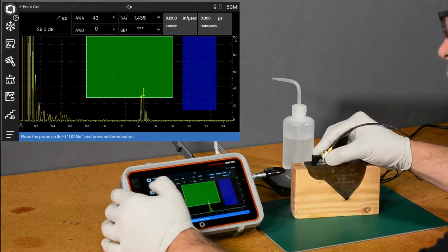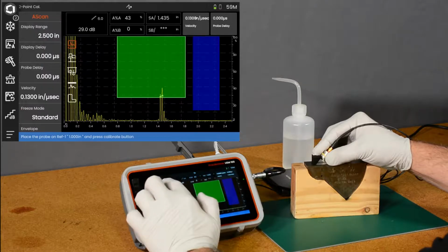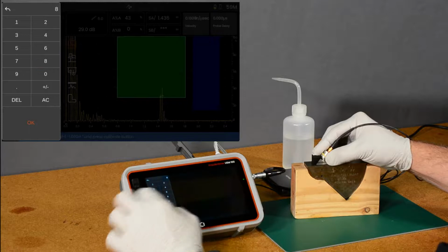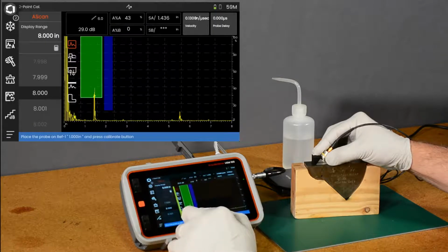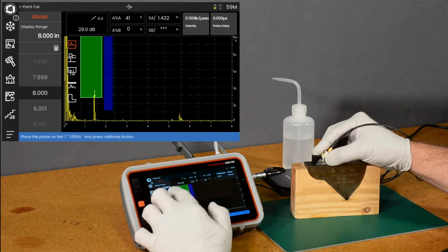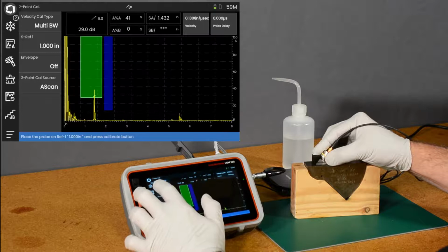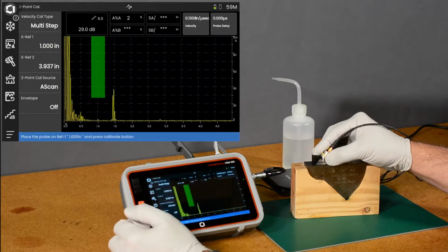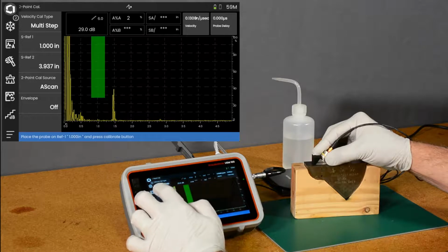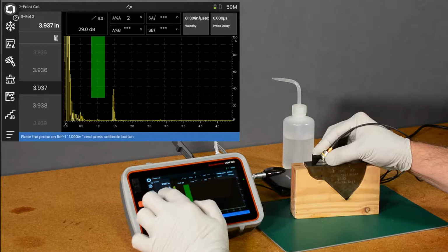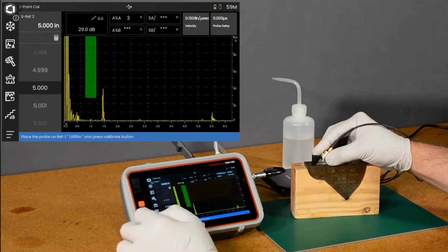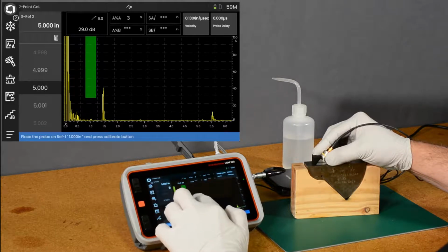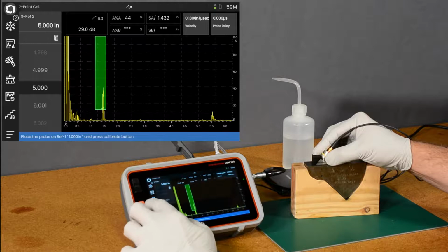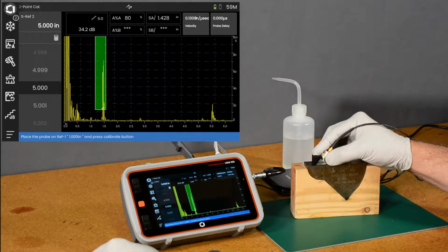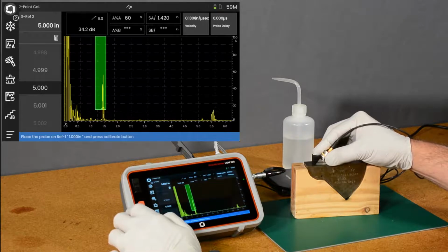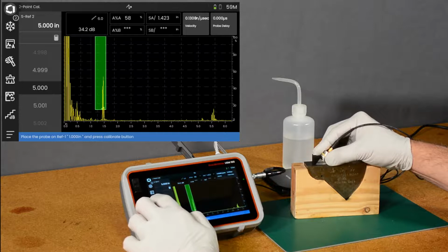So now if I extend my range out to, say, 8 inches, there's my echo at 1 inch, and I have an echo out here at 5 inches. So let's close that. We'll swipe out our sidebar, and we're going to go to multi-step calibration. And we're going to tell it that we want to have our first reference at 1 inch. We're going to do our second reference at 5 inches. Okay. We can drag our gate over the echo, and let's get that up to 80% screen height. Use the auto 80 feature to bring that up. Get it peaked up there.